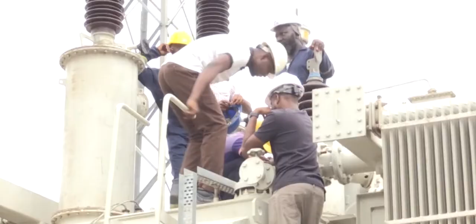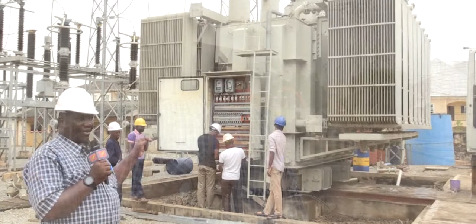TCN in-house engineers demonstrated their capacity again when they installed a 60 MVA transformer at Kubwa substation in Abuja. The principal manager transmission at the Abuja sub-region of TCN, Engineer Musa Shuaibu, said: We're able to couple everything now. The protection group, the TCN group, will now do their wiring. After the wiring, we will vacuum, then start filtration, then the pre-commissioning test will come up.